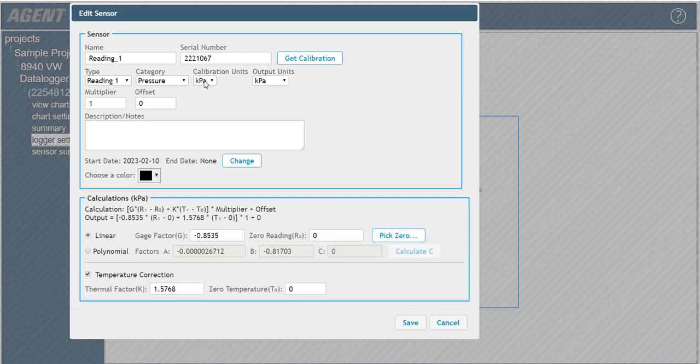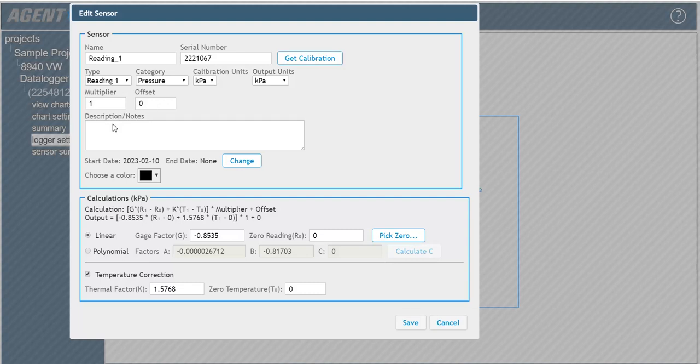The output units determine what unit of measurement will be used to display the data on charts. The multiplier field is automatically populated by agent with the factor needed to convert the calibration unit of the sensor to the user-selected output unit. The offset is an optional constant that can be added to the sensor output to adjust the data. The description and note field can be filled in at the user's discretion.